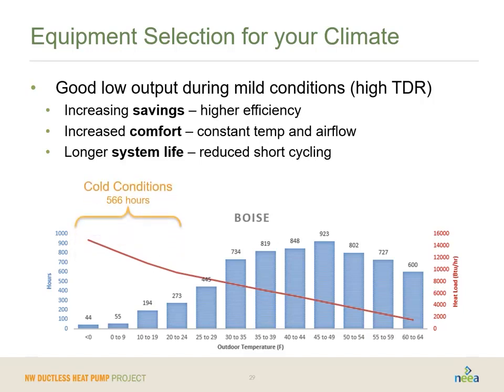Why? Let's look at it here. The coldest conditions, even in Boise, are 566 hours out of the year. The mild conditions in comparison are 3,000 hours a year. Think about which of these is a much bigger thing to overcome. You really want to make sure you're working well for 3,000 hours out of the year. It's the middle time between the really cold and the really mild, and that's where the well-weatherized home or the newer home that I mentioned can allow you to get away with a standard heat pump even in Boise. If you either have an unweatherized home or you are in another part of the east of the Cascades, that cold climate ductless heat pump is likely to be your best bet.